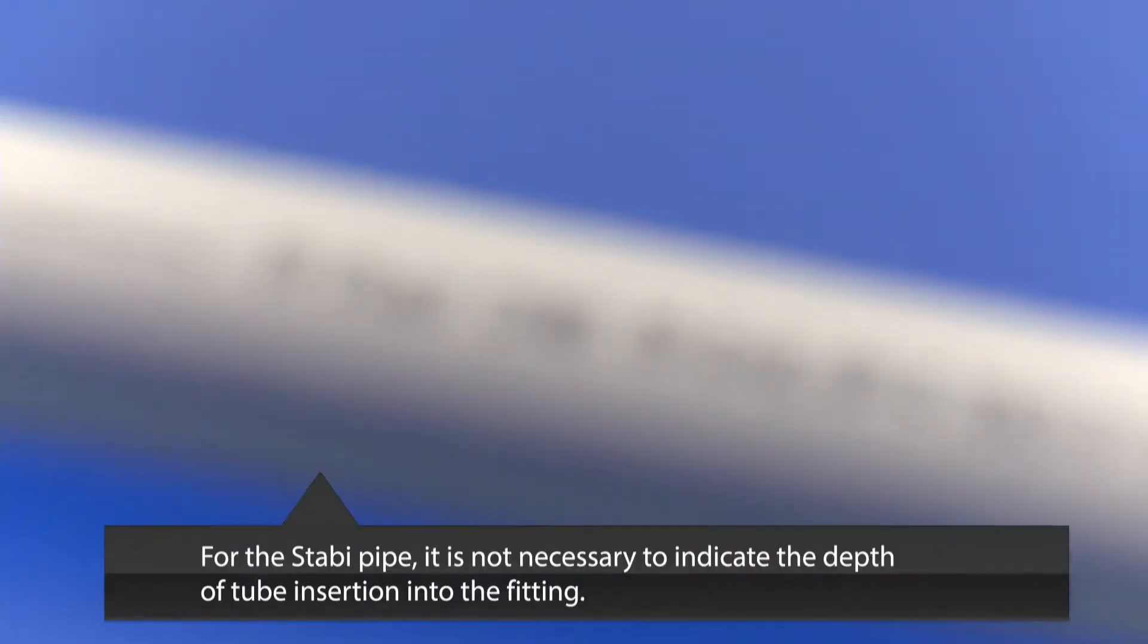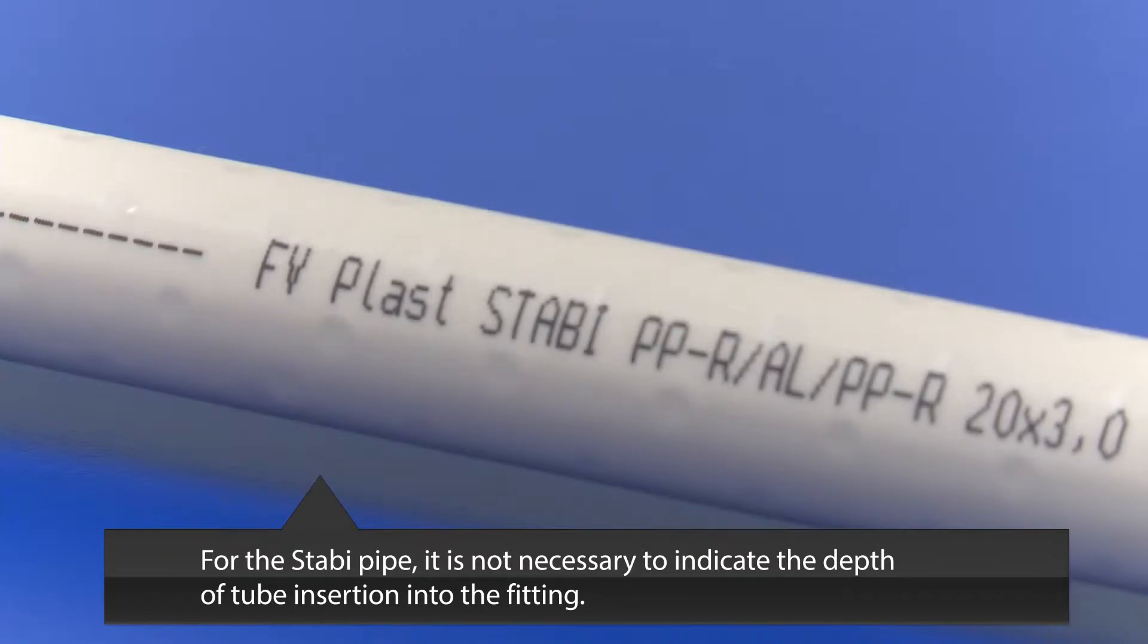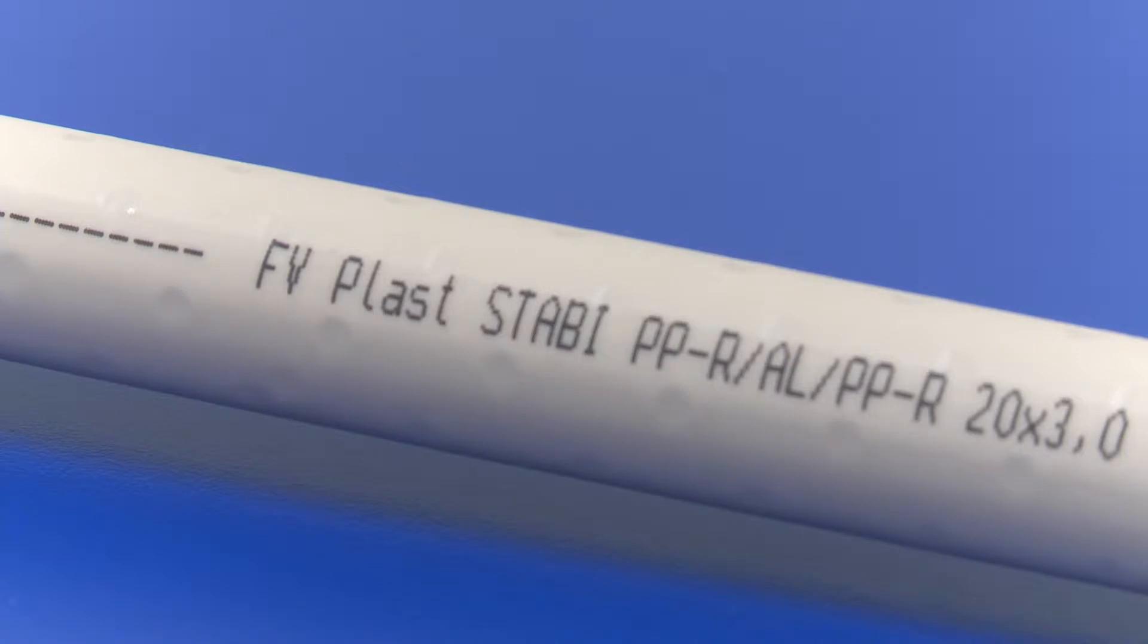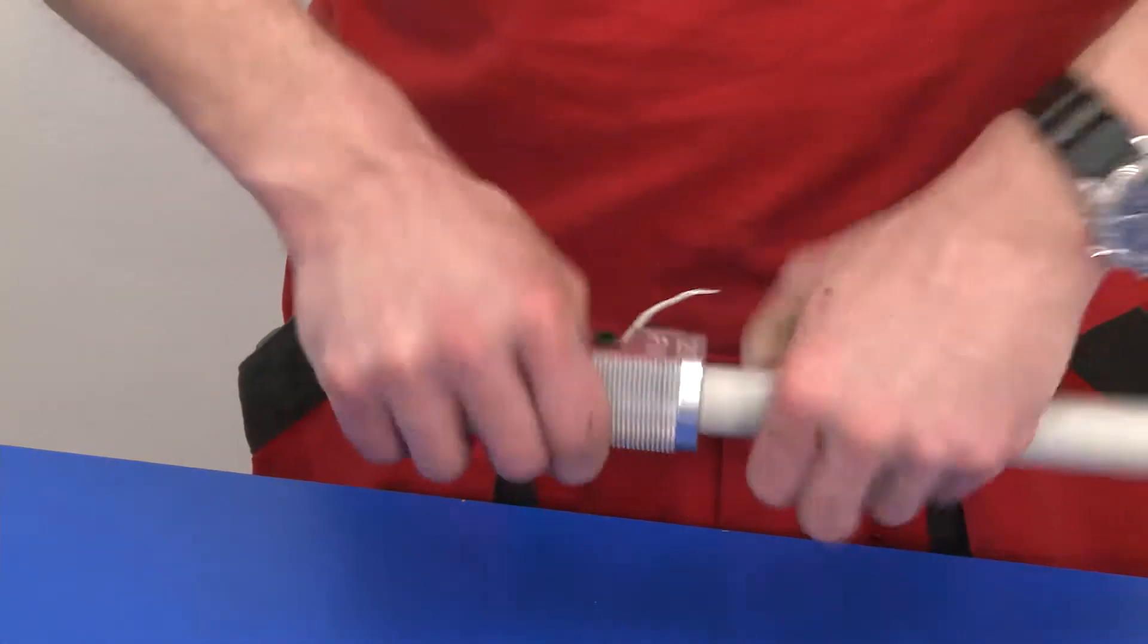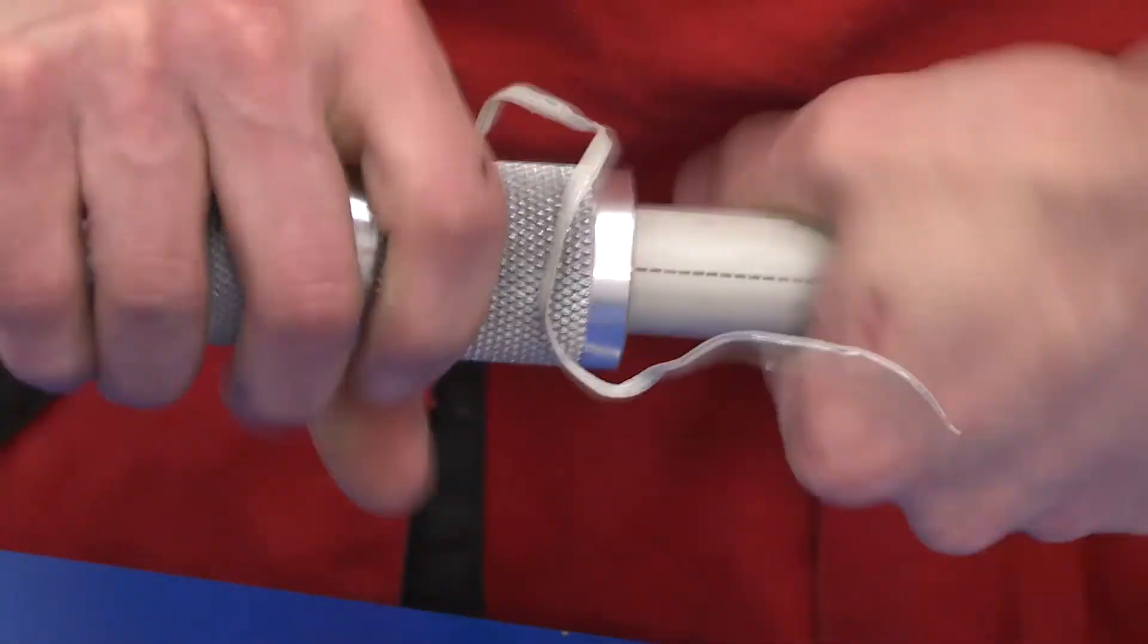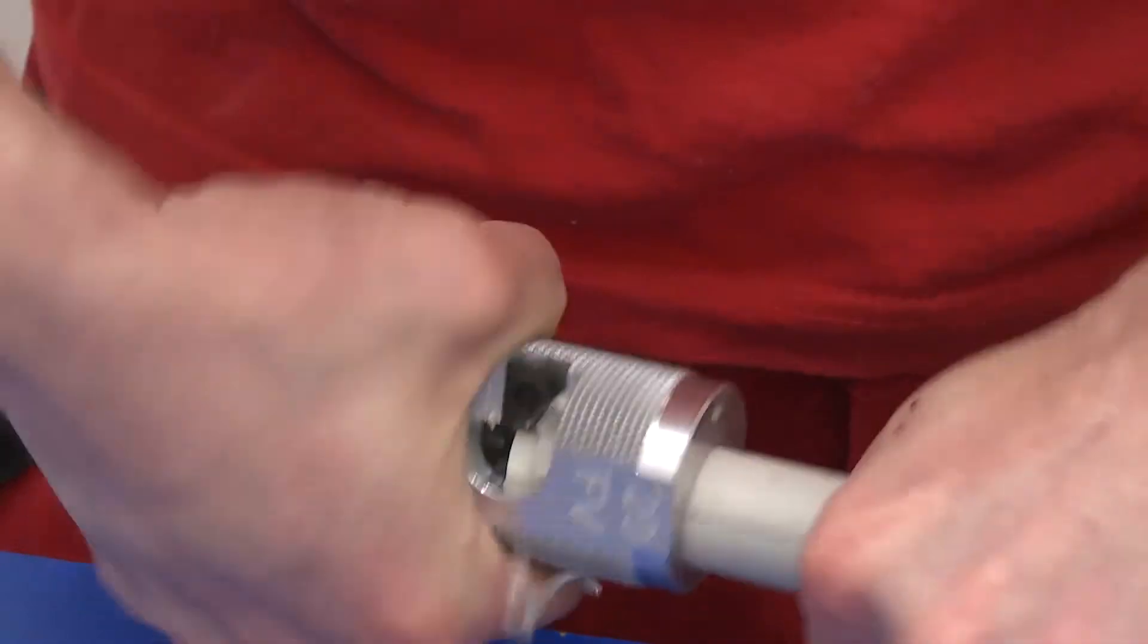If we connect the FV Plast Stabi pipe it is not necessary to indicate the depth of insertion of the pipe into the fitting. Before welding we remove the top plastic and middle aluminium layer evenly from the entire surface and to the desired length using a cutter. When doing this we keep a prescribed diameter for welding.